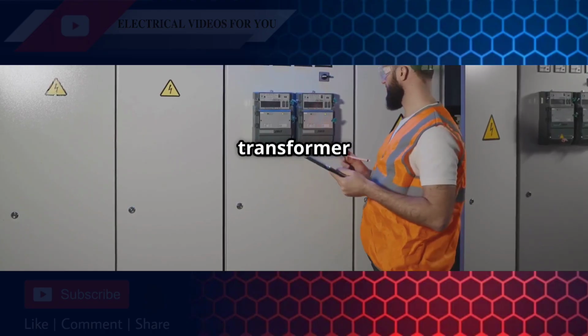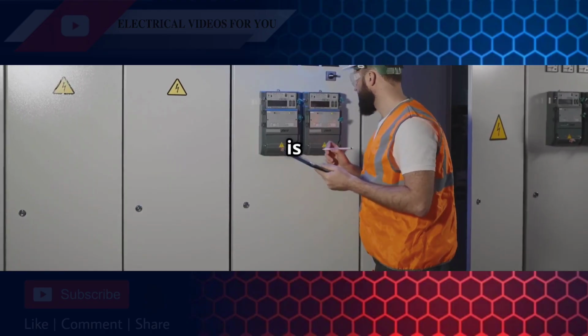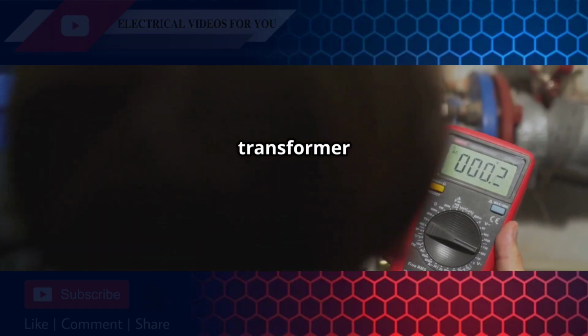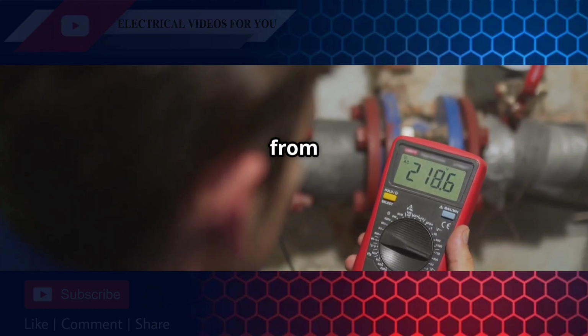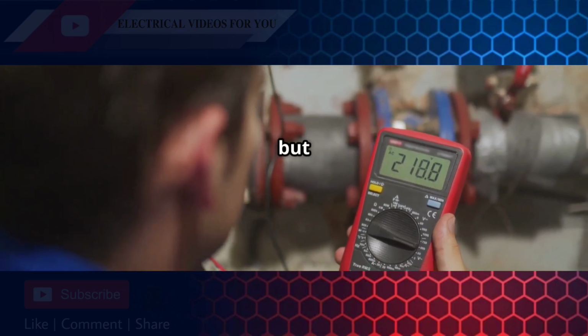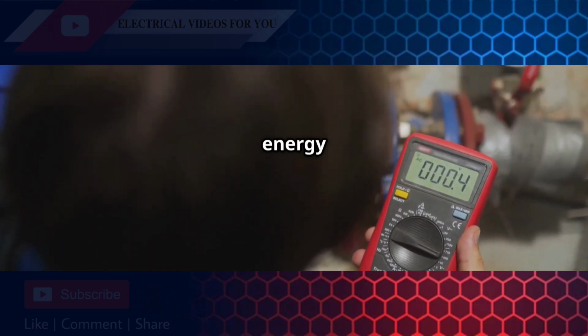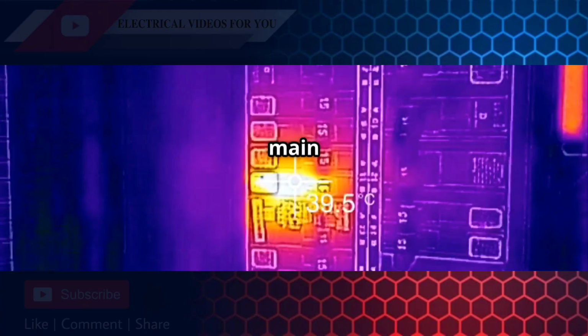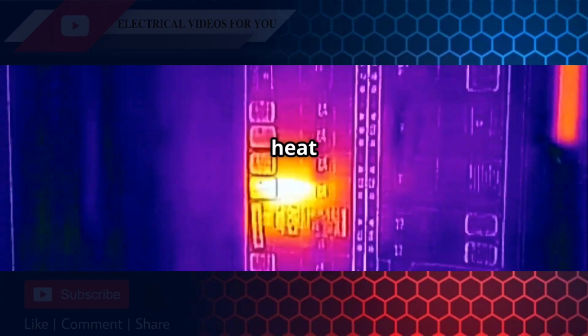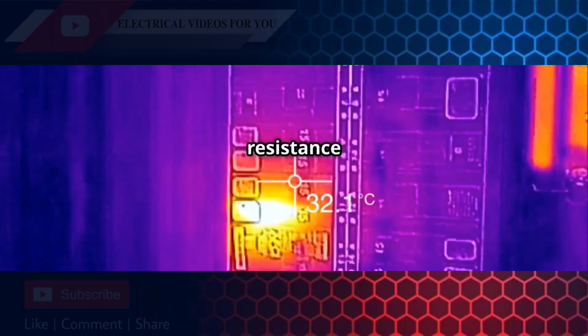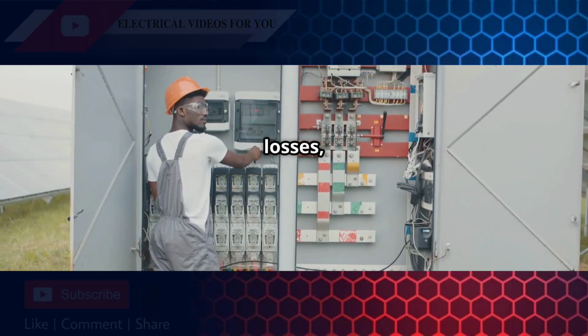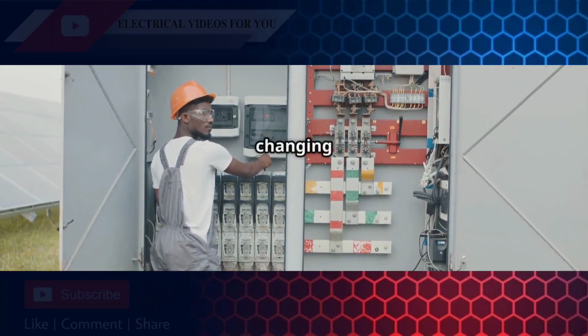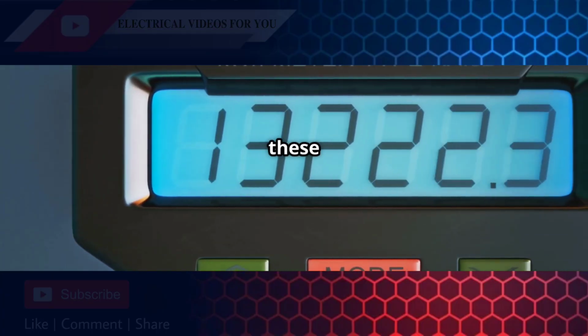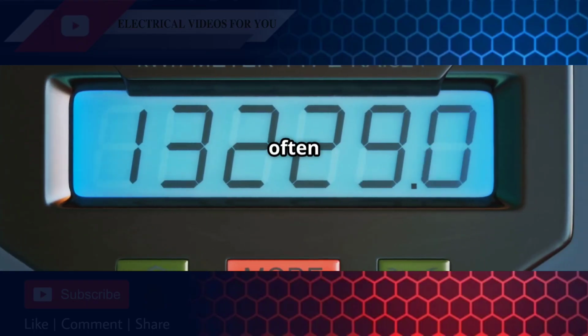So what makes a transformer good at its job? Performance is all about efficiency. An ideal transformer would transfer 100% of the energy from the primary to the secondary winding. But in the real world, there are always some energy losses. These losses come from two main sources: copper losses, which is heat generated by the current flowing through the resistance of the copper windings, and iron losses, or core losses, which are caused by the changing magnetic field in the core. A well-designed transformer minimizes these losses, making it highly efficient, often over 98 or 99%.